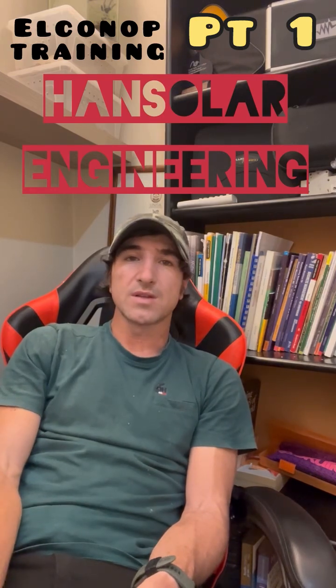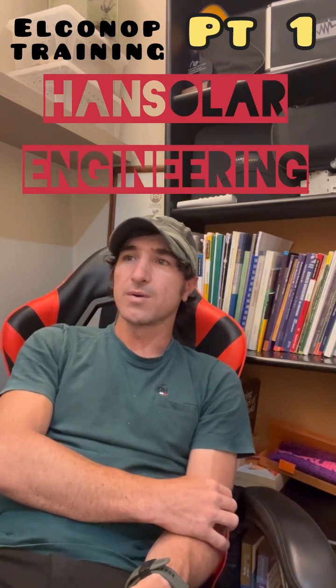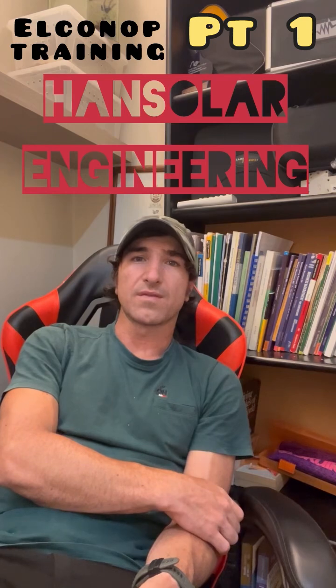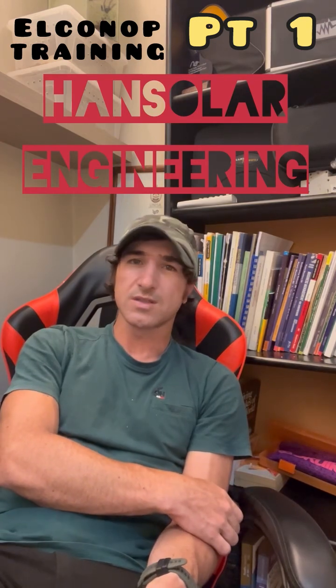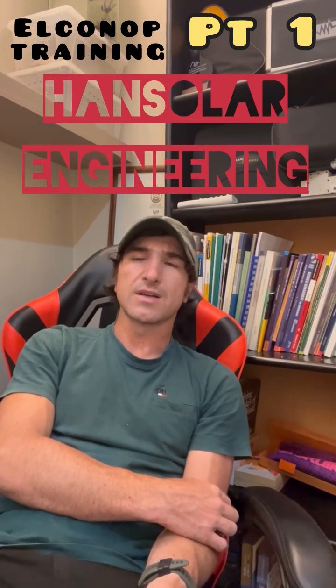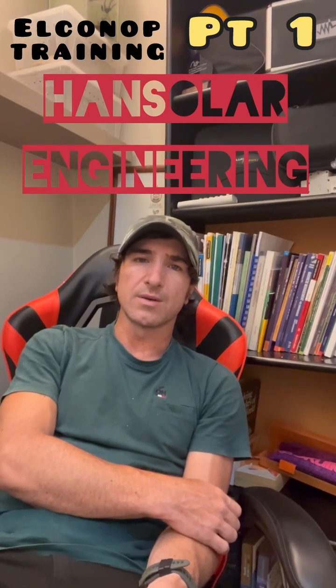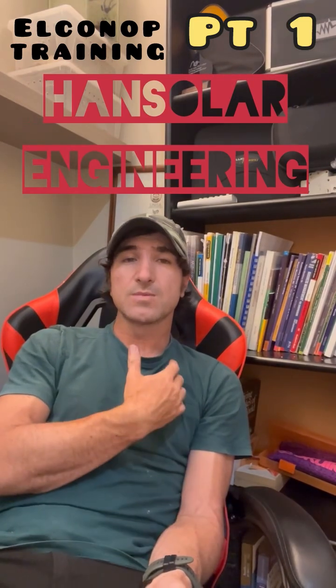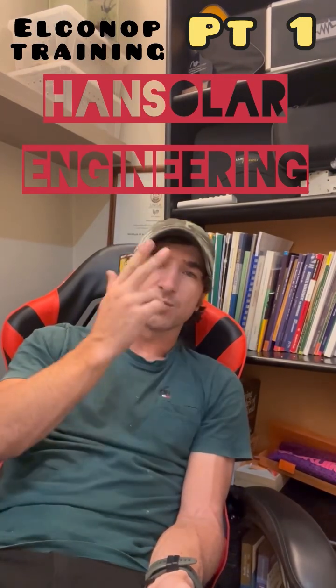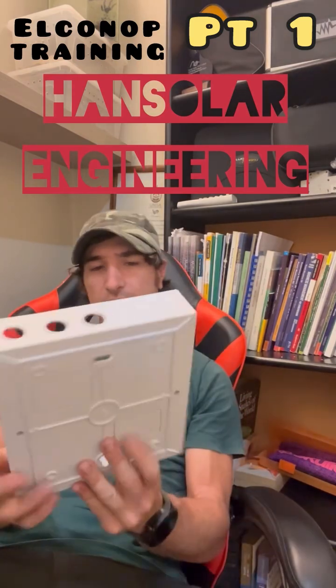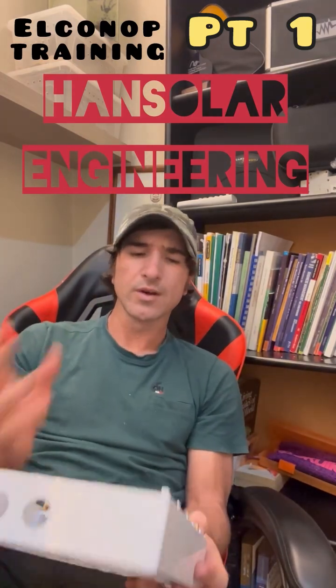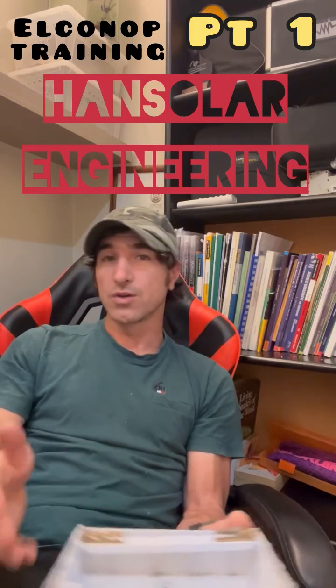Other sparkies have told me they size it by double. Yeah, it's a little bit of a problem sometimes, especially when you're dealing with a 5 kA and you can pretty much safely use a 6 kA. I'm not going to size it at like a 10 kA, you know what I mean? So that's just me personally. I know everyone will be like, oh, shoot my head off, but that's just my take on it. All right, so that's PSC of your circuit breakers, right?